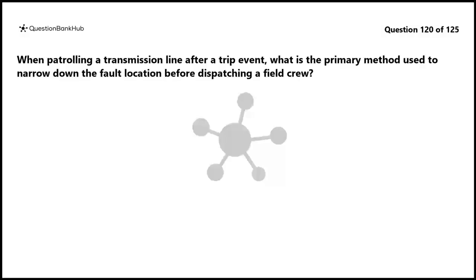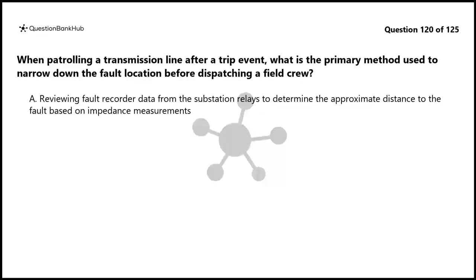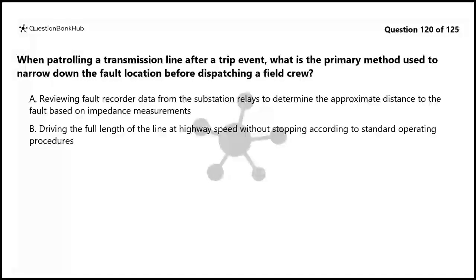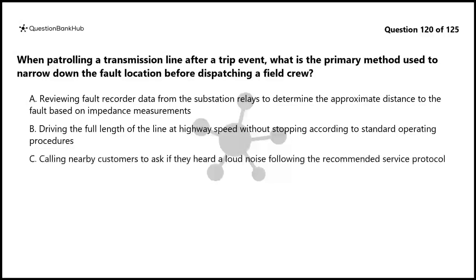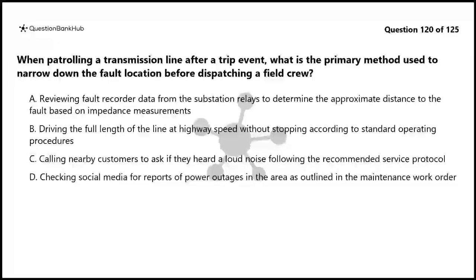Question 120. When patrolling a transmission line after a trip event, what is the primary method used to narrow down the fault location before dispatching a field crew? A. Reviewing fault recorder data from the substation relays to determine the approximate distance to the fault based on impedance measurements. B. Driving the full length of the line at highway speed without stopping according to standard operating procedures. C. Calling nearby customers to ask if they heard a loud noise following the recommended service protocol. D. Checking social media for reports of power outages in the area as outlined in the maintenance work order.